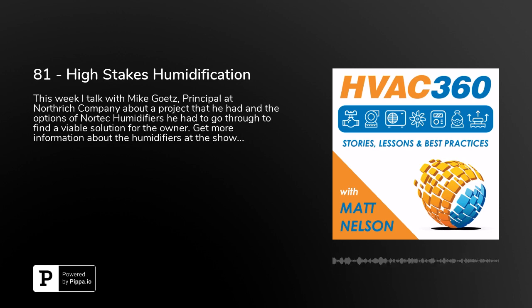I know that in a couple of different scenarios, being able to control humidity is a little bit of an issue. Is it relatively simple as far as humidistats being able to detect that? Are those going to get replaced as part of this project? They are not. They're going to use the existing ones they have now because they're getting the signal from the BMS, and they're currently pretty hidden. They're not out in the space where everybody can see them. So they will be able to utilize what they already have, which saves some cost, since they already have a building management system in place.